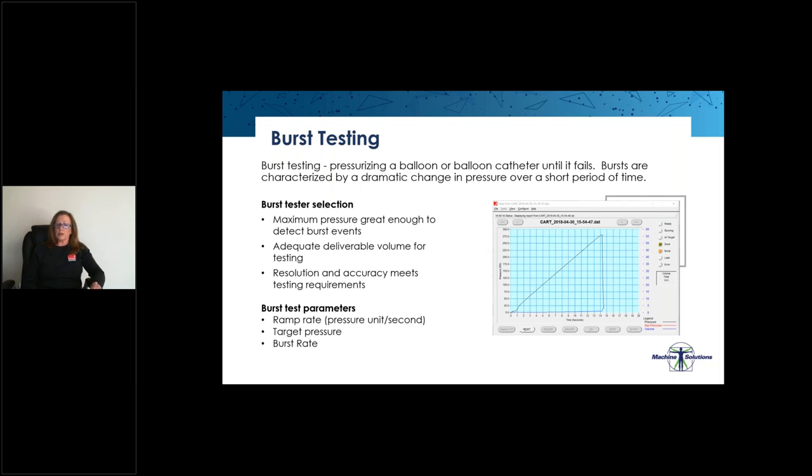Burst test parameters to consider when we're developing a burst test include our ramp rate, target pressure, and burst rate. When we're selecting our ramp rate, it's usually dependent on the type of product that we're testing, as well as maximizing our test time. For instance, if we're testing a catheter with a very small lumen, we're going to need to select a slower ramp rate due to flow restriction. If we're testing a catheter that is more compliant and larger, we can go faster with our ramp rate, but we do need to be careful not to go too fast as to lose control of the ramp. We should set our target pressure higher than the pressure that we expect our product to fail, and the burst rate should be set in order to trigger burst conditions.